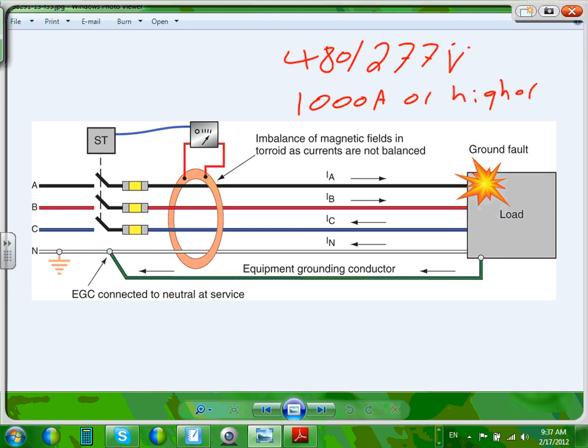If you have a system 1,000 amp or higher, you have to provide something called ground fault protection. We will do that one in the industrial because that's what we have. We have a 4,000 amp switchgear. What this is looking at, guys, is the ground fault.